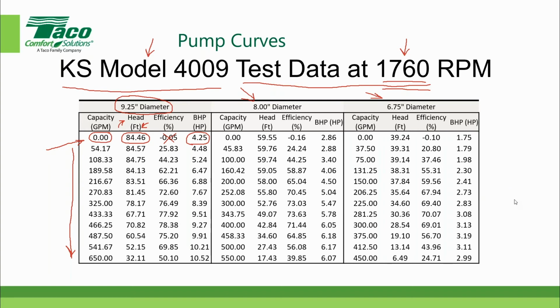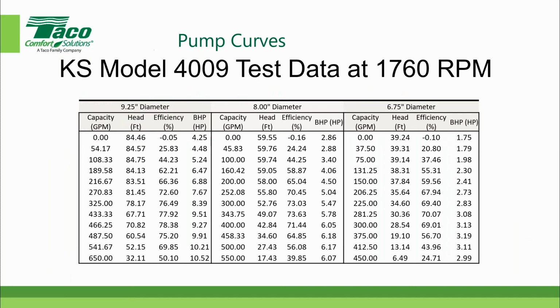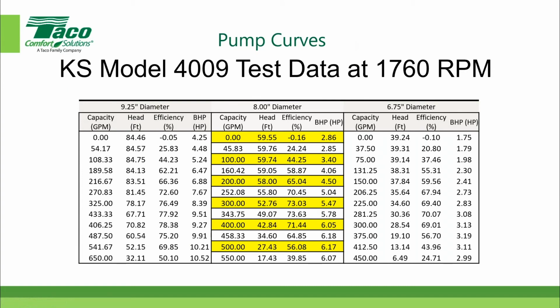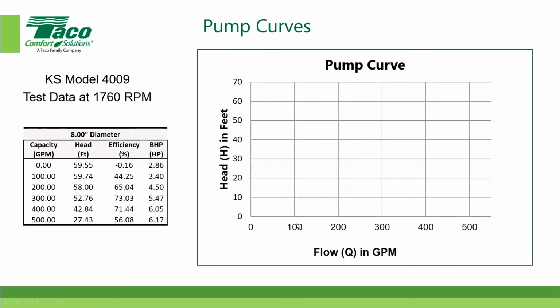What do we do with this pump performance data? Well, we plot it on a curve. So let's go to the next slide and take some of the data for an 8 inch diameter impeller, move it over here to the left. Now we're going to plot it on that same chart that we plotted the system curve, only in this case, we're going to start off at 0 gallons per minute. I'll grab my pen here. At 0 gallons per minute, we have roughly 60 feet. So there's 0 gallons per minute, roughly 60 feet. I'll put a data point right up there. 0 gallons per minute, 60 feet. There's the first data point.